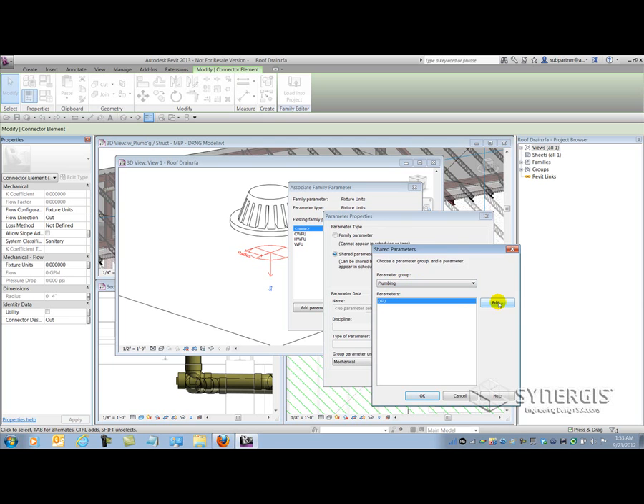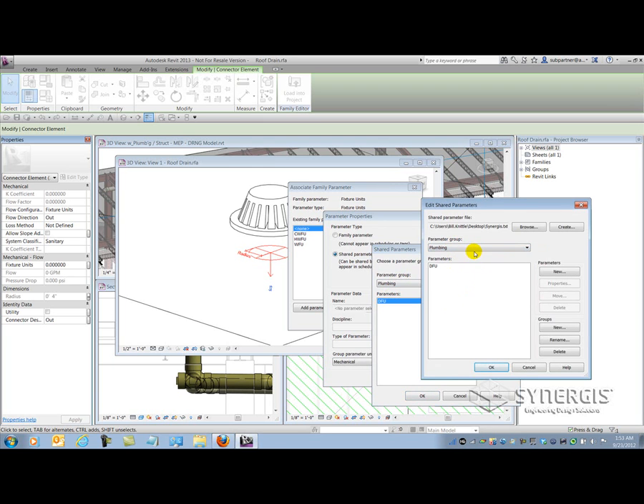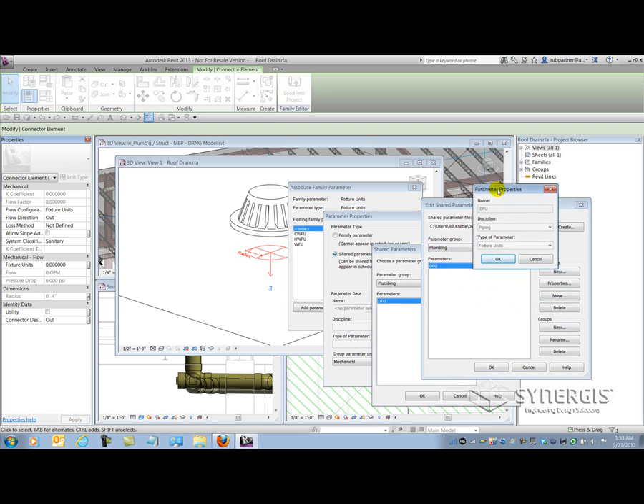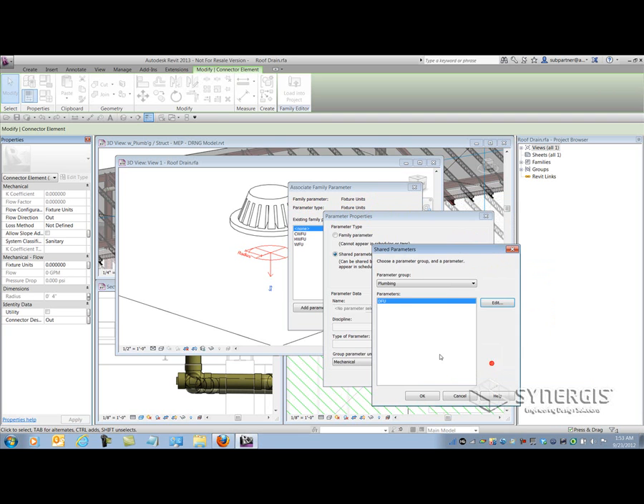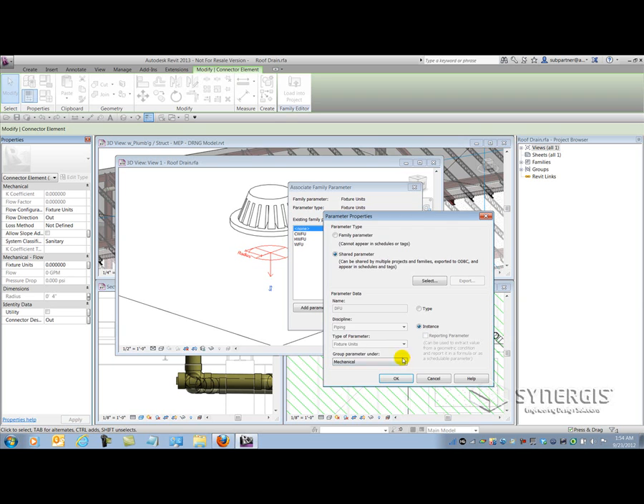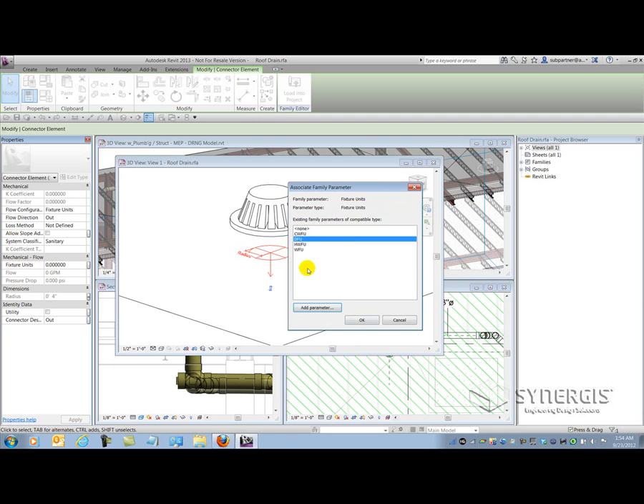If I hit Edit to take a closer look at the shared file — you can have one shared parameter file for your whole company because you can group your parameters. I built a group called Plumbing and a parameter called DFU. Looking at the properties of the shared parameter, I set the discipline to Piping because I've got to be able to associate fixture units — which is the parameter type in my shared parameter file — back to the original fixture units parameter. It's very important these two work together; if you don't, you'll get inconsistent units and Revit won't like it. I hit OK, pick that parameter, make it instance-based under Mechanical Flow, and it pops into the list inside my family.